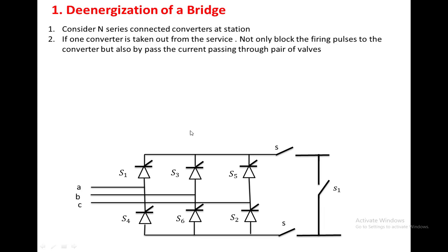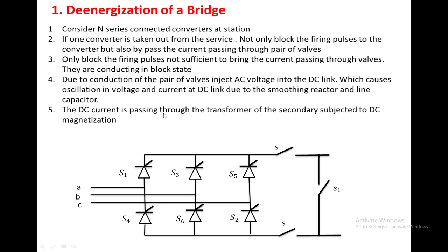Here we have taken one converter, and converters are connected in series. If you want to remove this converter, you should not apply any pulses to these valves — that is called blocking. During blocking, some amount of current is passing through the valves, so the AC voltage will be reflected on the DC side, producing oscillations due to the smoothing inductor and capacitance of the DC link. Moreover, the secondary winding of the transformer carrying DC current will cause DC magnetization. So not only do we block the firing pulses to the valves, we also have to bypass the current passing through the conducting valves.